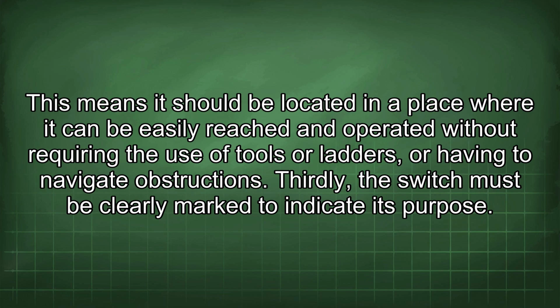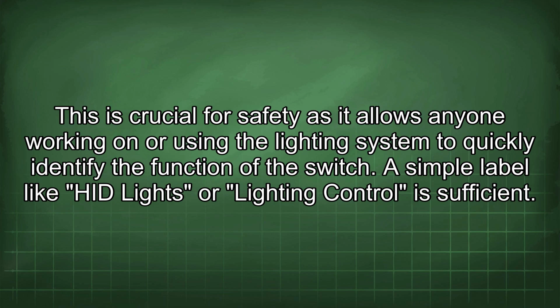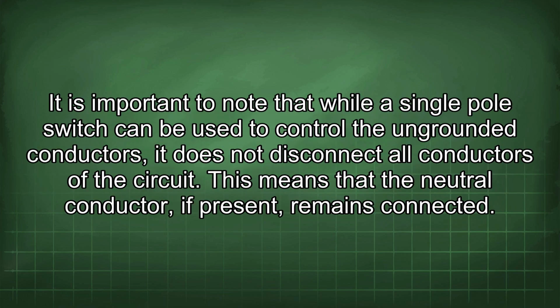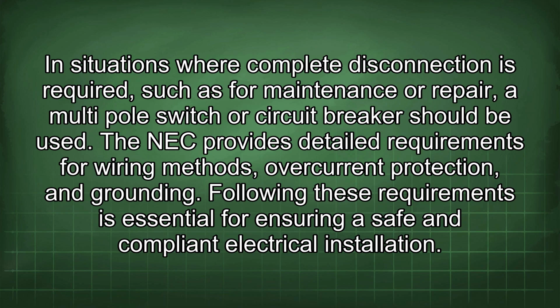Thirdly, the switch must be clearly marked to indicate its purpose. This is crucial for safety as it allows anyone working on or using the lighting system to quickly identify the function of the switch. A simple label like HID lights or lighting control is sufficient. It is important to note that while a single-pole switch can be used to control the ungrounded conductors, it does not disconnect all conductors of the circuit. This means that the neutral conductor, if present, remains connected. In situations where complete disconnection is required, such as for maintenance or repair, a multi-pole switch or circuit breaker should be used.